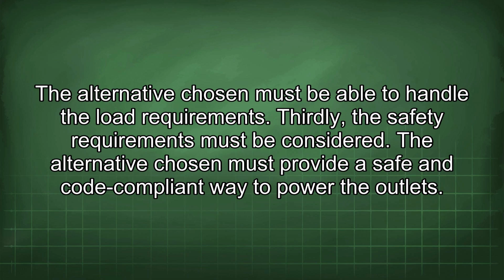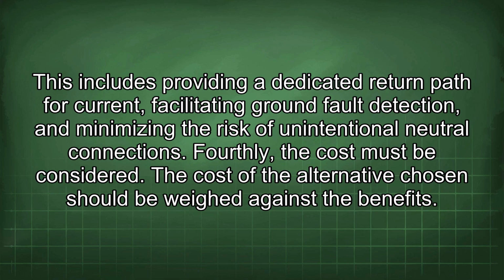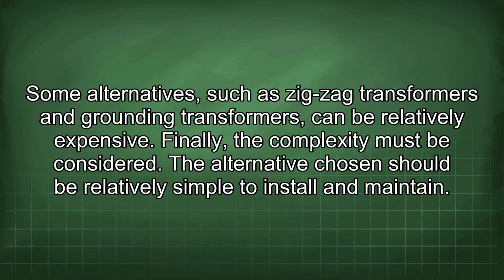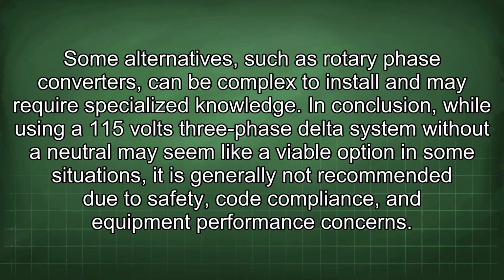Thirdly, the safety requirements must be considered. The alternative chosen must provide a safe and code-compliant way to power the outlets. This includes providing a dedicated return path for current, facilitating ground fault detection, and minimizing the risk of unintentional neutral connections. Fourthly, the cost must be considered. The cost of the alternative chosen should be weighed against the benefits. Some alternatives, such as zigzag transformers and grounding transformers, can be relatively expensive. Finally, the complexity must be considered. The alternative chosen should be relatively simple to install and maintain. Some alternatives, such as rotary phase converters, can be complex to install and may require specialized knowledge.